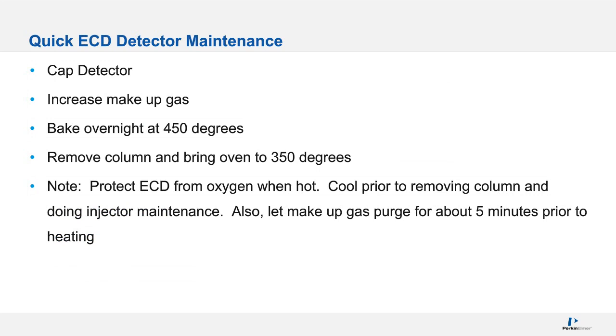I put this in for ECD maintenance. Cap the detector. Instead of cleaning an anode and going through that, usually if you bake the detector out, it recovers. So I cap the detector, bring up the makeup gas, wait 5 minutes to get the oxygen out, bring it up to 450 degrees. Sometimes I actually remove my analytical column and bring the oven up too to really give it a good bake. You could do it overnight, or you could just watch the millivolt reading go down on the readback.